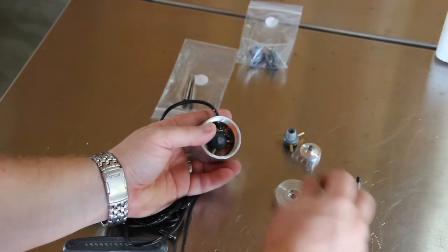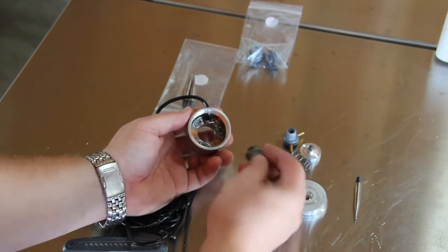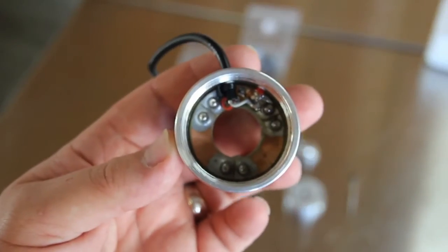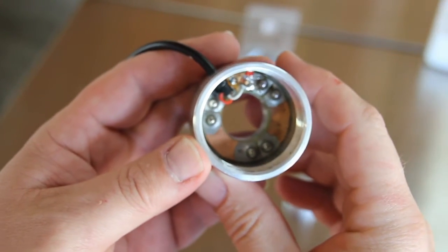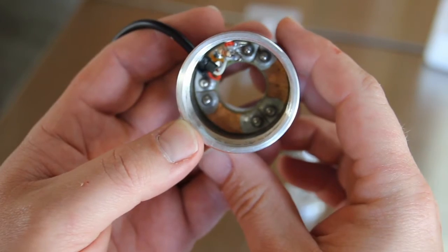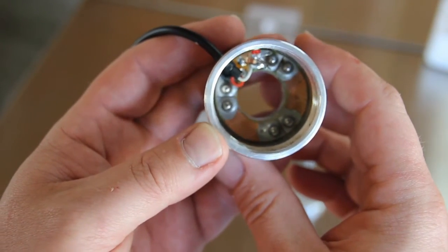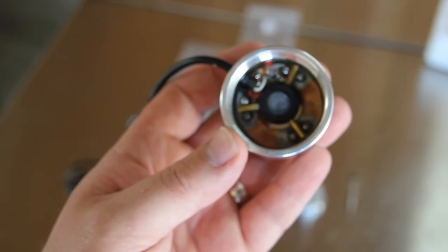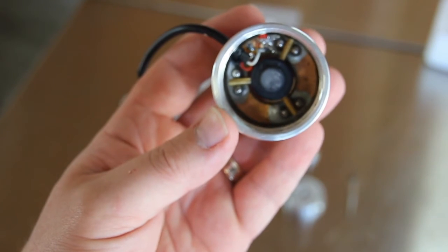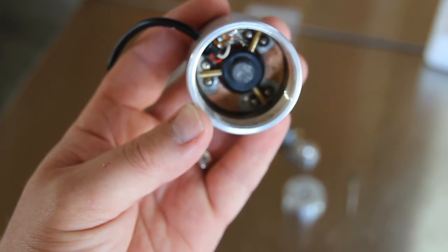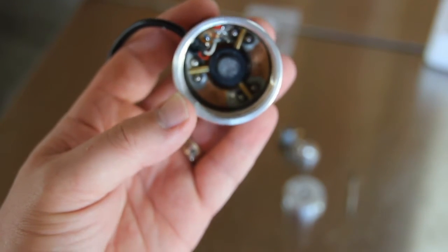There's a spring that holds the hub in place. There's the hub, and then we'll get a close up here. So that's inside. So you can see there's the ball bearings on the circuit board, the LED, the wires coming in, all of that's there. So when the hub is in place, it sits in place like so, and the brass pins make contact across the ball bearings, and that means that the probe is not touching anything. Then when the probe moves and removes the brass pin from the ball bearings, then it sends the signal that it's touching.